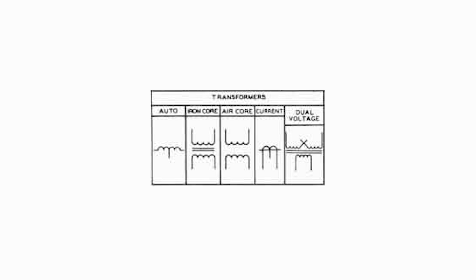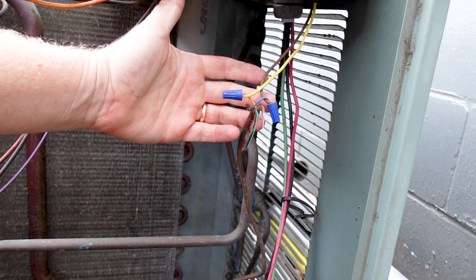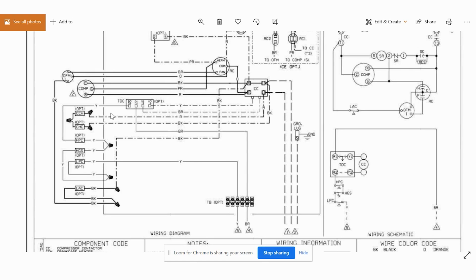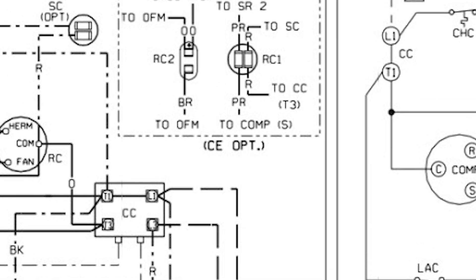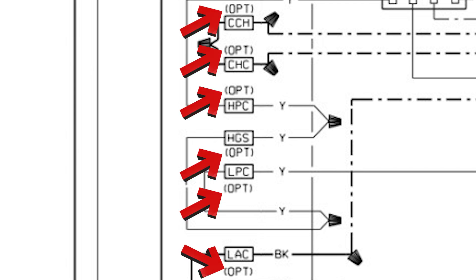If it had a transformer in it, then they would show the transformer symbol here. But because the condenser doesn't have a transformer in it, the only wiring that's coming into it is this yellow and brown that's feeding the low voltage of the contactor. Also on this side here on the pictorial side or the point-to-point diagram side, they're showing that a lot of these things are optional. So you'll see here, it says optional OPT here.